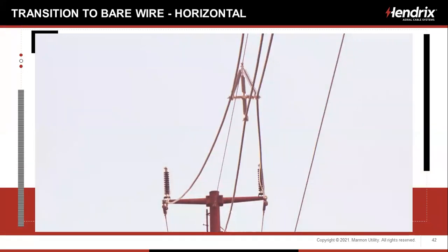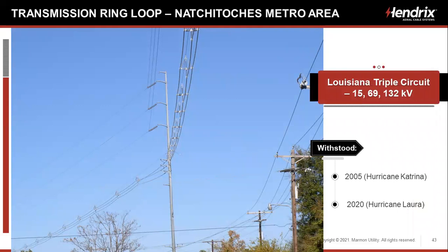Here's a horizontal transition. And again, we've worked with utilities. Anything they want to do, as long as it meets National Electric Safety Code, we're happy to do it. There's a triple circuit in a city called Natchitoches. Forgive me for mispronouncing that, in Louisiana. They had a 132 kV bare wire on top, a 15 kV bare wire on the bottom, and they wanted to install a 69 kV bare wire. I believe what happened here is line crews balked. They said, there's no way we're working on bare wire in between 132 and 15 kV. Switched that to spacer cable and saved a tremendous amount of vertical clearance there.